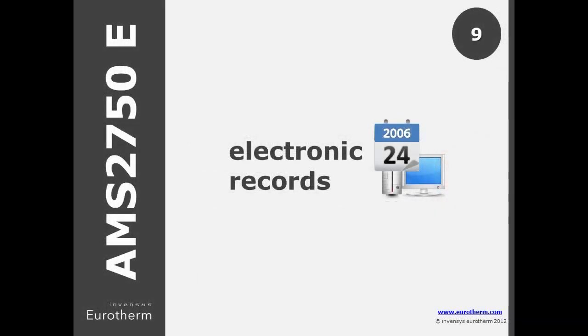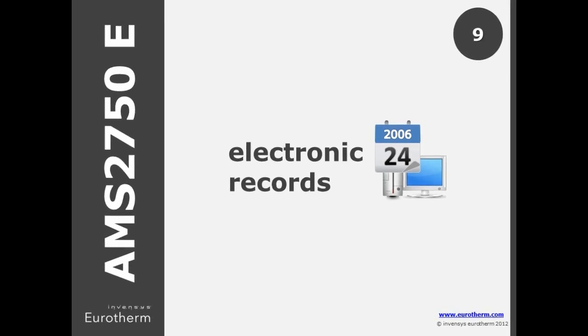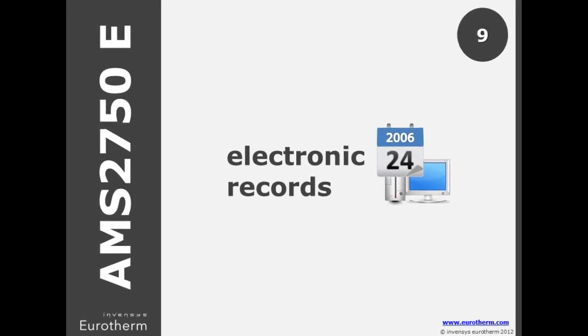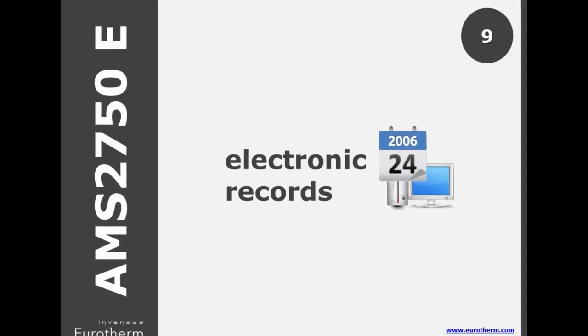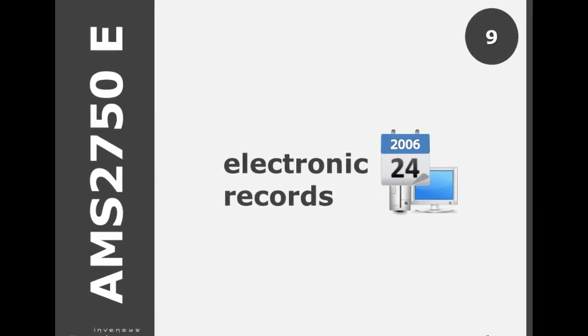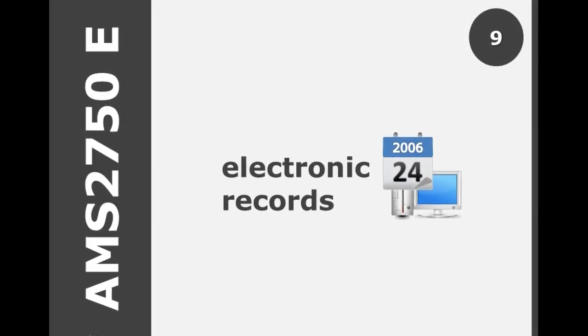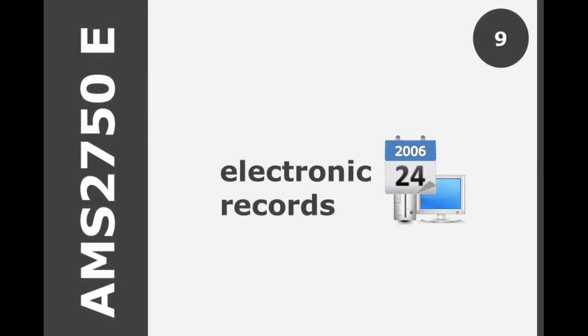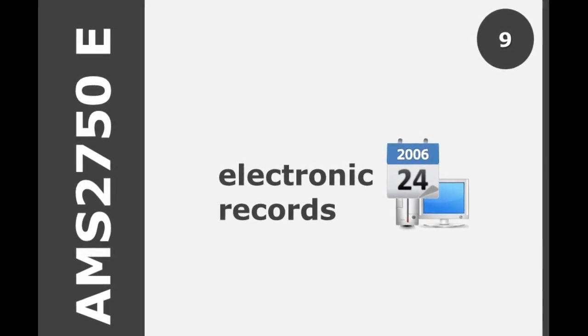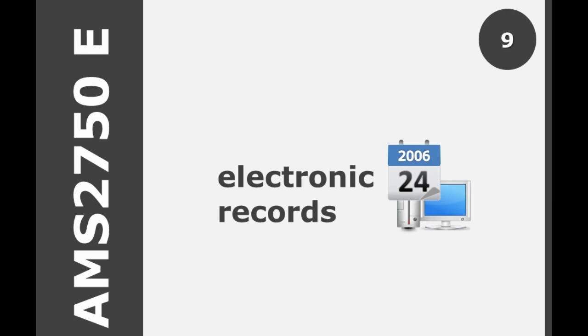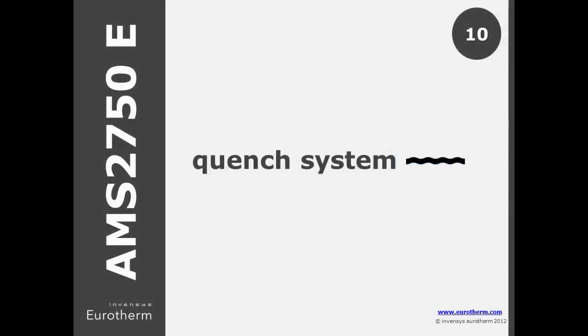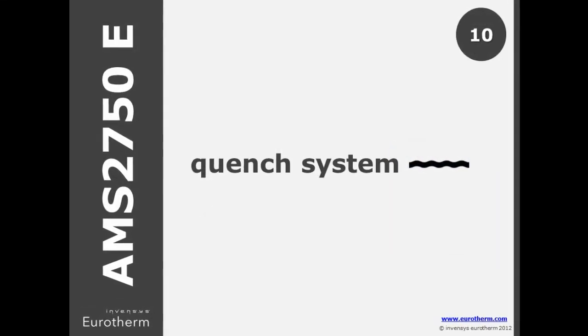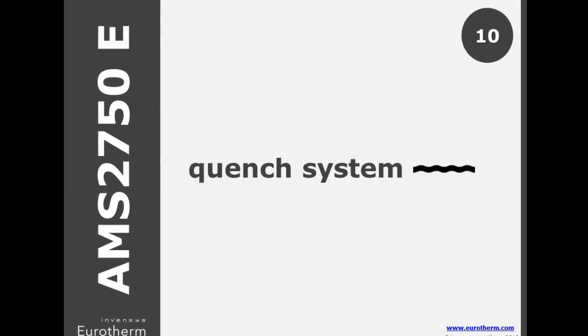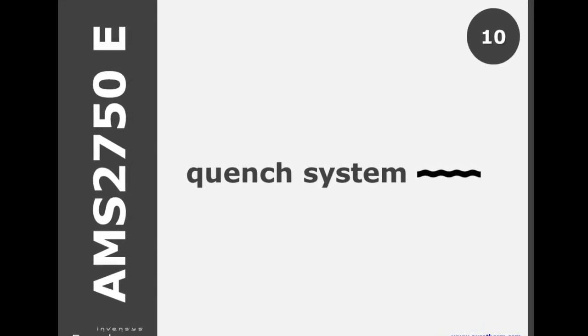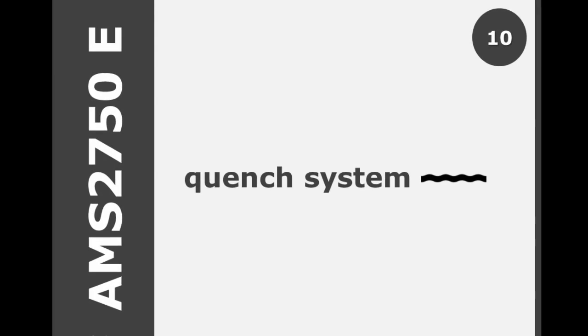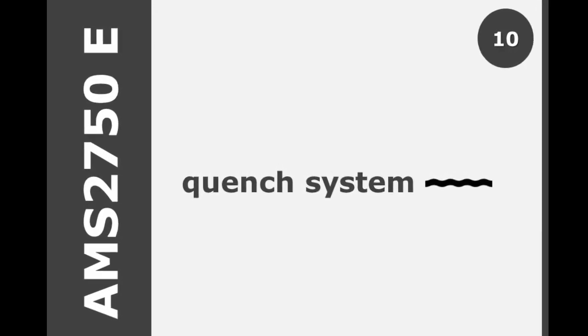Detailed in E, any systems purchased after September 2006 or any electronic record after 2015 must ensure that the electronic records cannot be altered without detection, and an additional statement outlines that the system must be capable of providing evidence that the record was reviewed. Quench systems installed before September 2005 do not require mandatory recording until July 2015. If installed after the September 2005 date, they must be recorded.